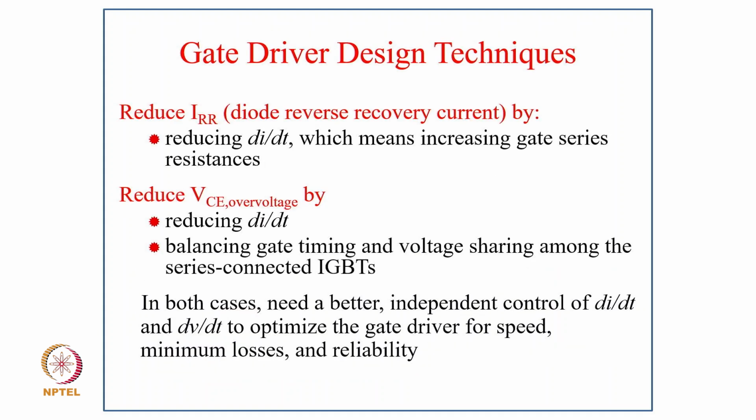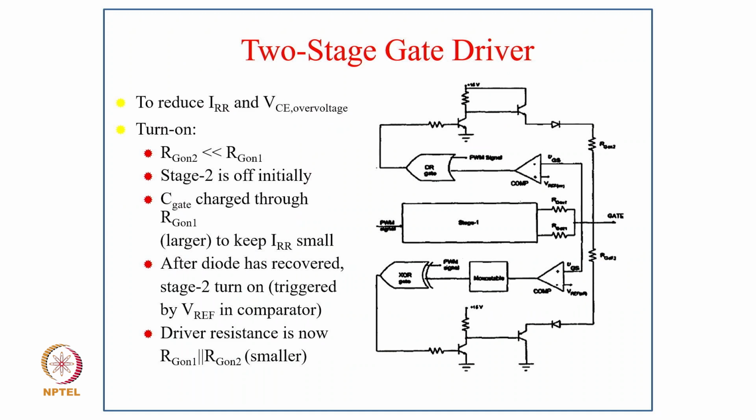So now, gate driver design techniques. Typically we have to reduce IRR, the diode reverse recovery current, by reducing the di/dt, which means increasing the gate series resistance, and reduce VCE overvoltage by reducing the di/dt and balancing gate timing and voltage sharing among series connected IGBTs. In both cases, we need better independent control of di/dt and dv/dt to optimize the gate driver for speed, minimum losses and reliability.